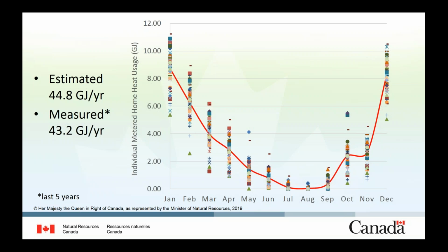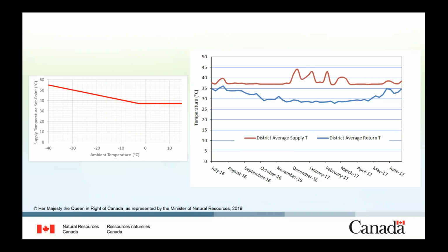On the left here, what we have is the set point supply for the air handlers for the district heating system. As I mentioned, most of the time we operate at 37 degrees. Once the temperature goes below -4, the supply temperature goes up. In this area, it's not uncommon to reach -30 in terms of ambient temperature, so at that point we will supply at around 50. So this is the set point, and on the other side is the measured supply and return temperatures. As you can see, most of the time we are supplying at around 37 degrees and the return at 28. This is important because it increases the efficiency of the solar collectors and also increases the available energy in the borehole thermal energy storage, even without the use of a heat pump.